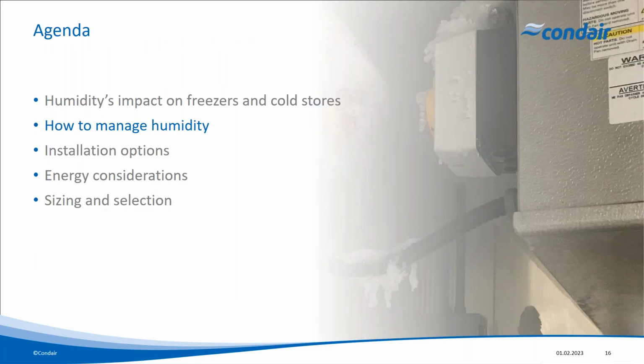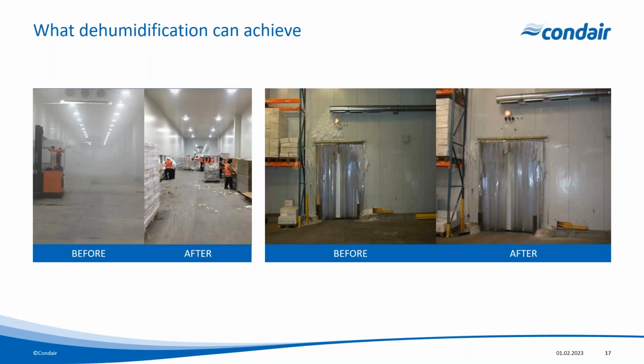So how do we manage humidity in the space? Well, this is what we can achieve. This is the picture that we saw earlier where we had fogging appearing. We take the air out of that store and we run it through a dehumidifier. And actually it doesn't take an awful lot of moisture removal to rapidly reduce that fogging. This is running a dehumidifier for 20-25 minutes, and we can reduce fogging really dramatically.